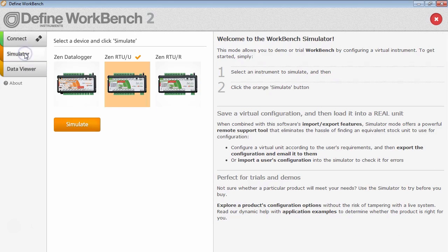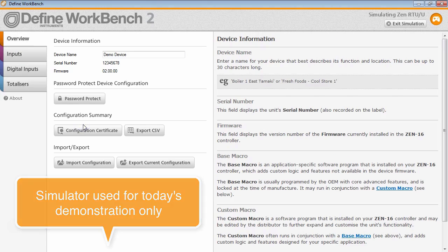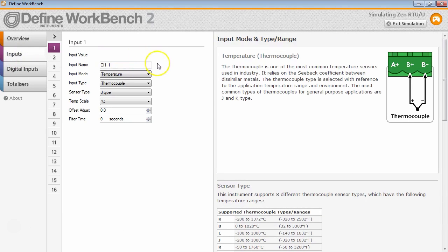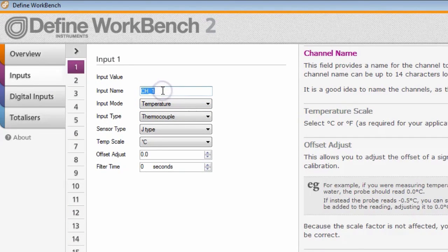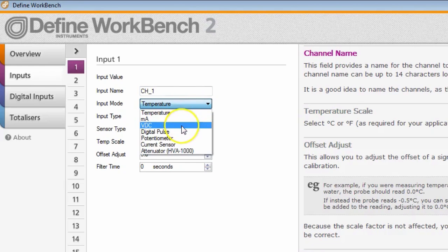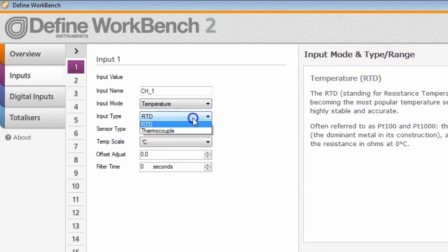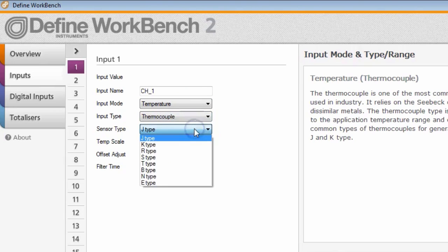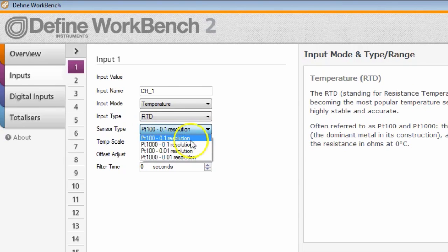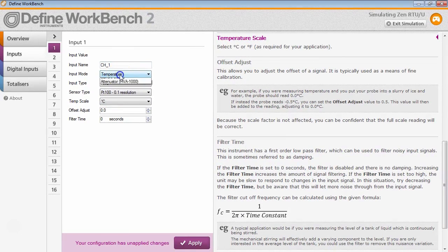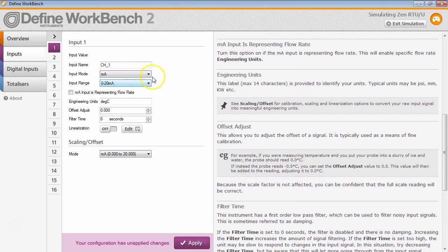Today I'm going to just go in through the simulator, and I'm going to select Zen RTU, and take you to the inputs page and just show you some of the input setups. You'll notice that the 16 channels are shown down the side, and for each channel you can specify the name of the channel and the input mode: milliamps, volts DC, temperature, digital pulse meter, potentiometer, current sense, attenuator, and so on. So if we select temperature, we can select RTD or thermocouple, various types of thermocouple, RTD, different resolutions, 0.1 degree or 0.01 degree resolution, and temperature scale and so on, and filters. And you'll notice that each time help is given on the side here, which is very handy. So setup of the inputs is fairly straightforward. Go through all your 16 channels and select what input mode you want.